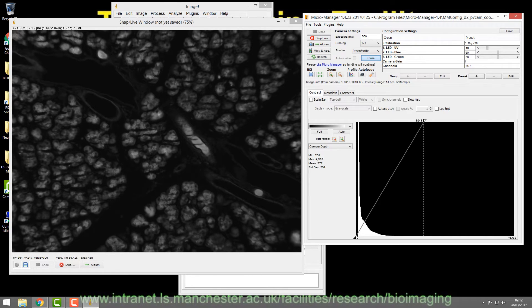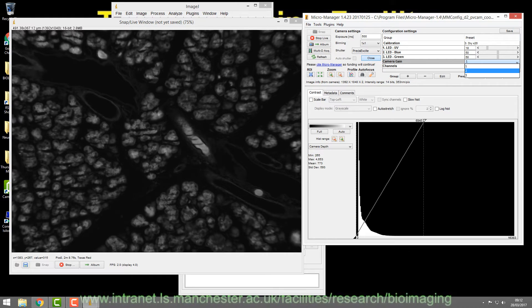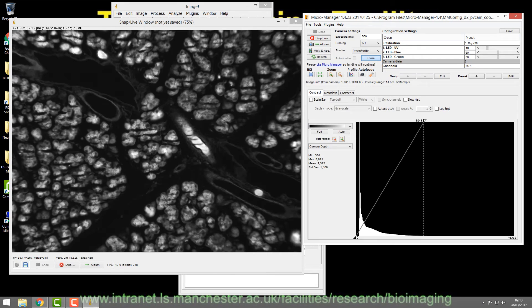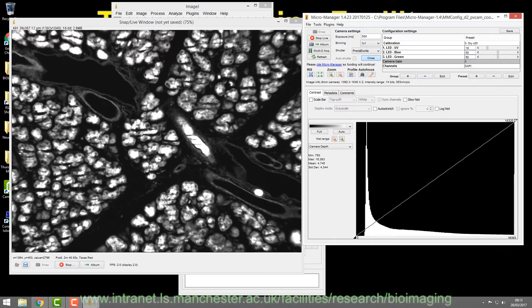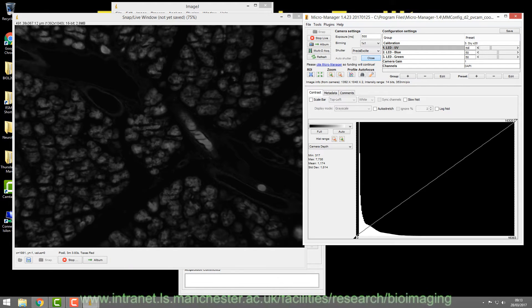Every time you start a MicroManager session, the LEDs all drop to 50% as a default starting point, so you have to adjust them each time. There's also camera gain: gain 1 uses the full pixel bit depth and full well capacity. Gain 2 appears to boost your signal, making it easier to saturate — it assumes the pixel will become half full and divides that into 16,000 shades of grey. Gain 3 is even brighter. If you have a dim sample, changing the gain state is really useful, but it's much easier to saturate.